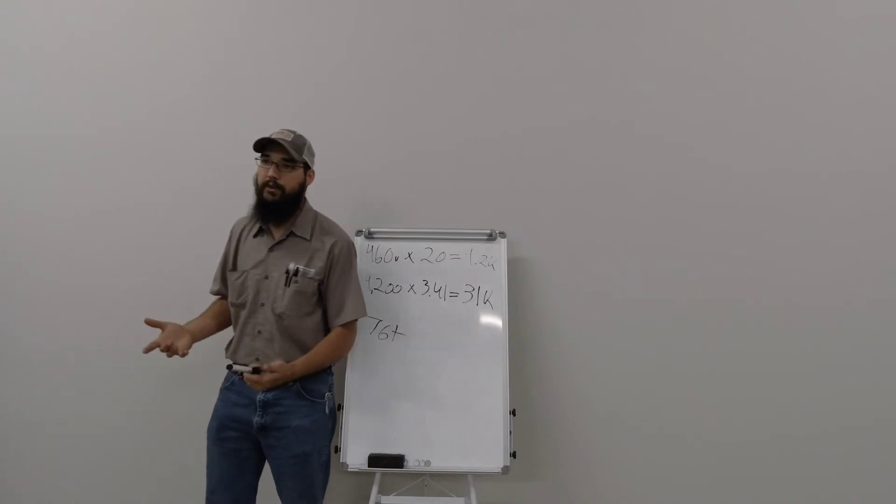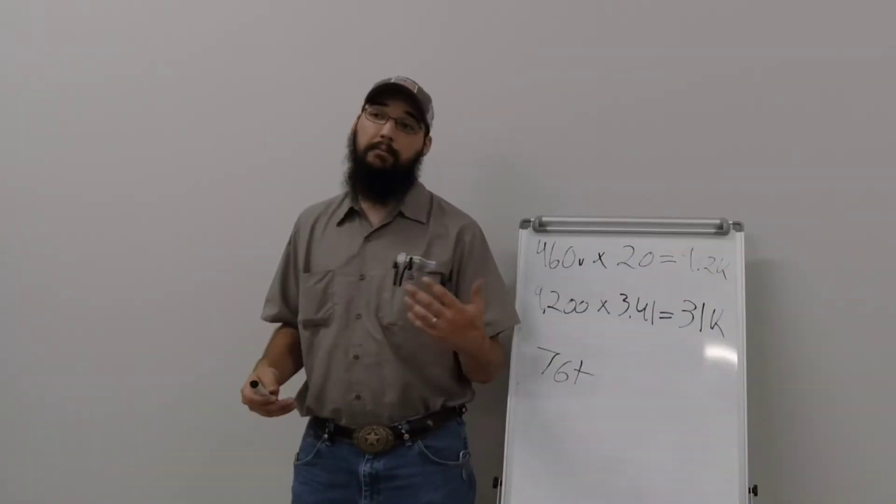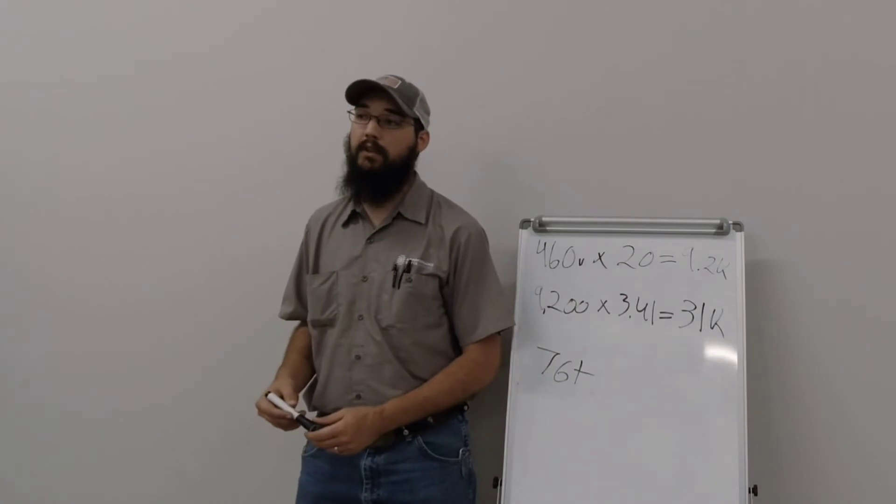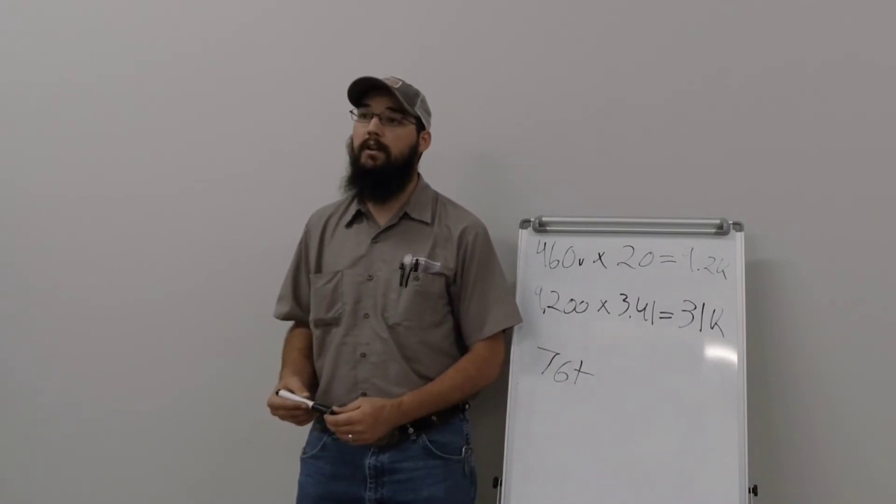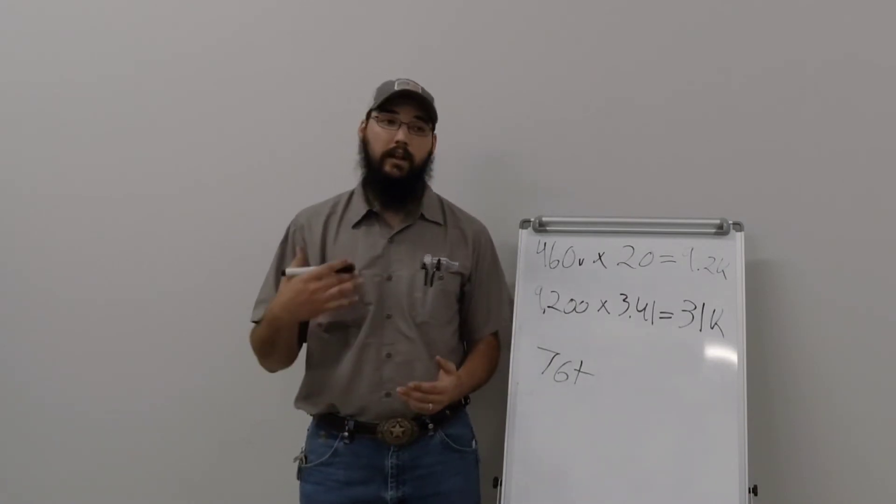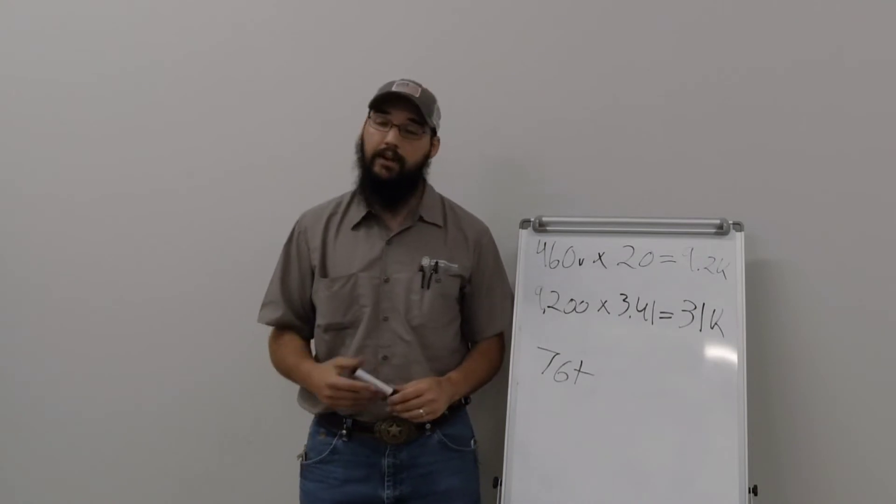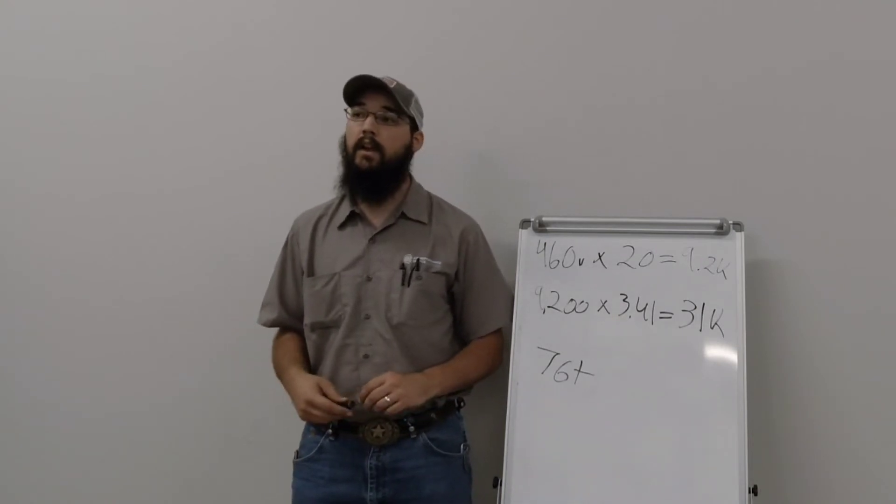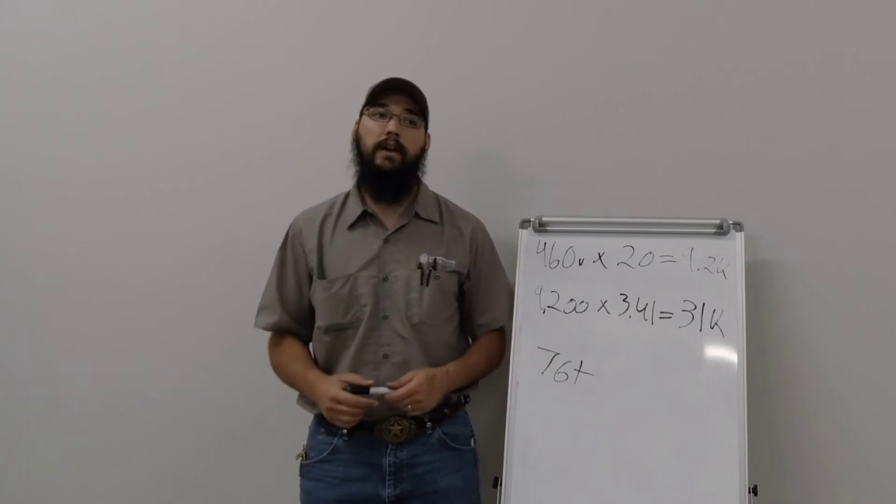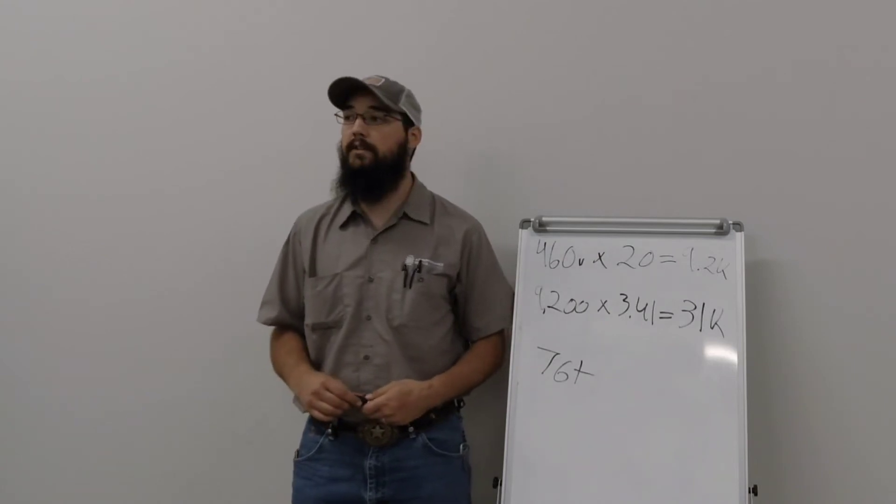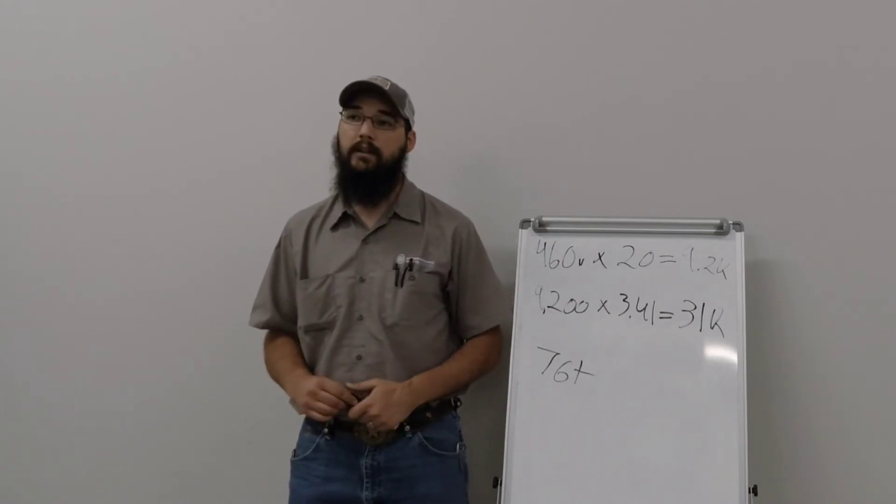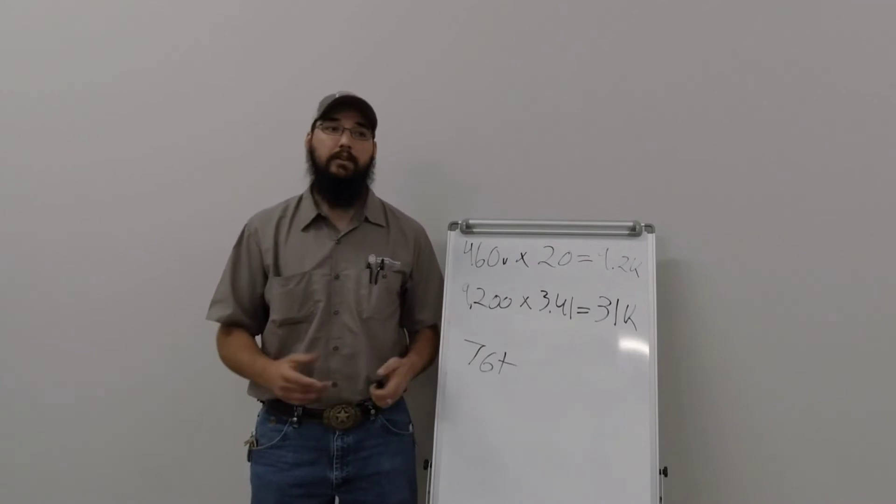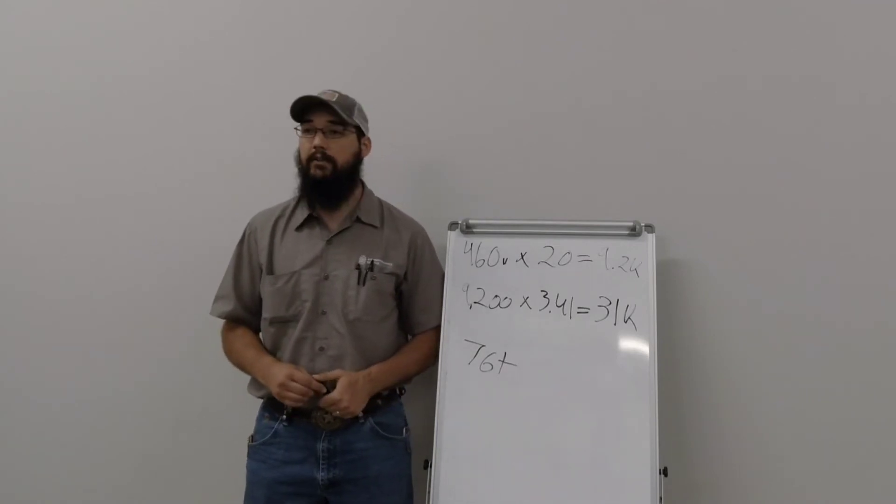And then anything below 70, specifically, I would consider a low load. In some cases, like the McQuay self-contains or even the Trane self-contains, they don't really perform all that well until that return gets up to about 72 or above. And one of the ways you can help determine their load is by how fast the fan is spinning.